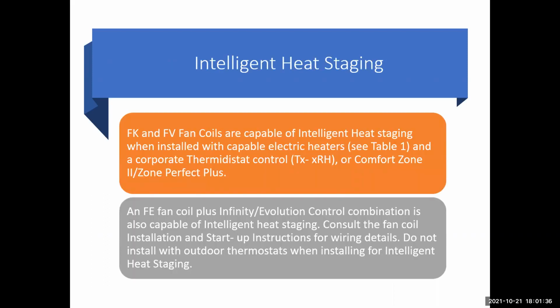Intelligent heat staging. The KF and the FK and the FV fan coil units are capable of intelligent heat staging when installed with a capable electric heater. And that's what was kind of shown on that table 1 that we were talking about earlier. And a corporate thermostat, which is like the TP or the T6, and to be the NRH or the PRH, or a Comfort Zone 2 or Zone Perfect Plus zoning kit.